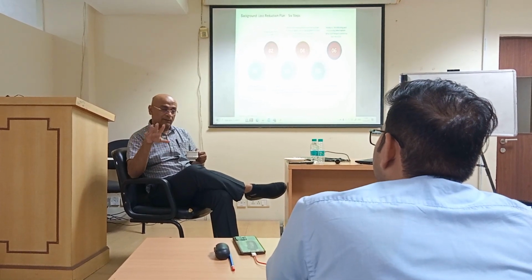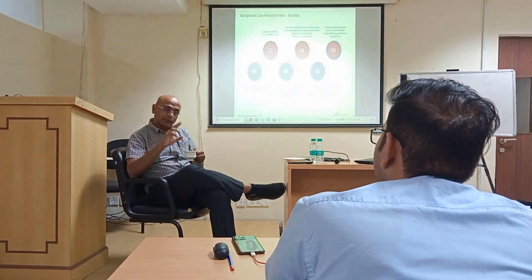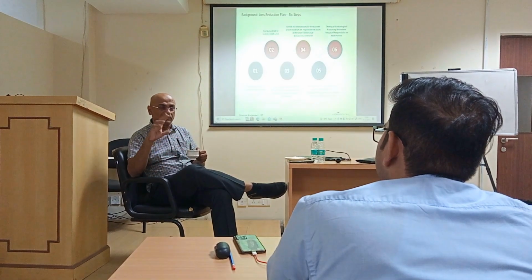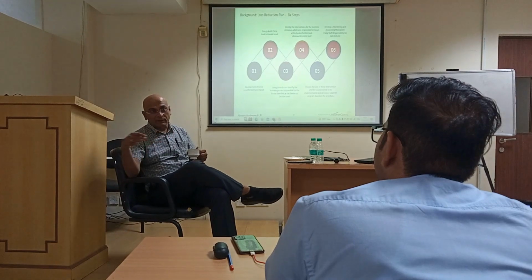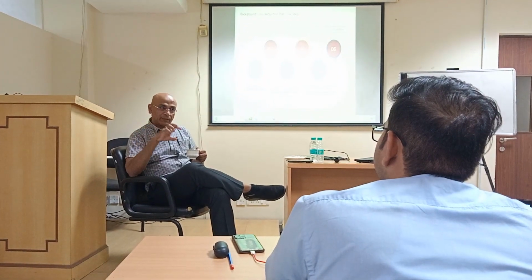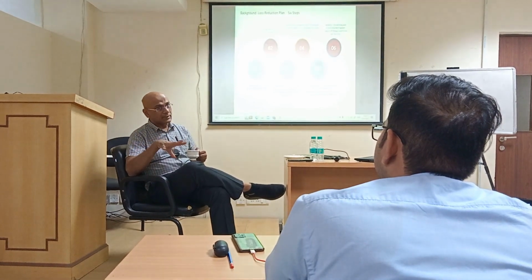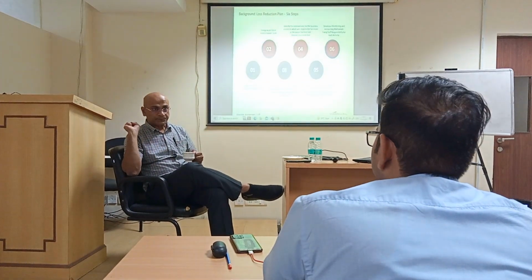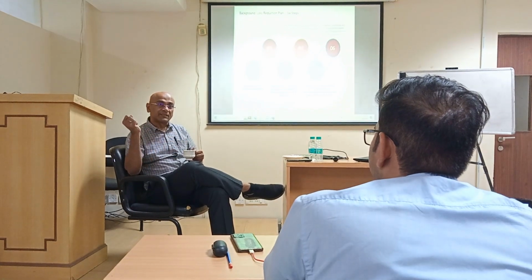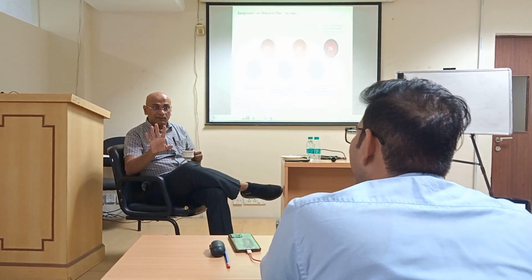We were a 7-member team. One person was technical from Secure Meters. I was there as a metering expert. Then there was one commercial expert. So we had 7 people with different perspectives looking at it. At the end of that 4-week, 5-week exercise, we calculated the losses. It came to 76%, 77%. I said, this is only T&D loss. Commercially, I have not considered it.